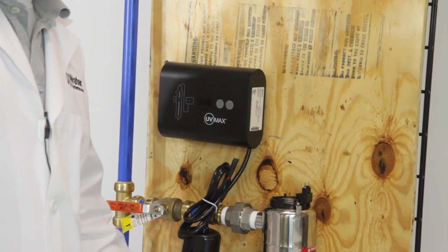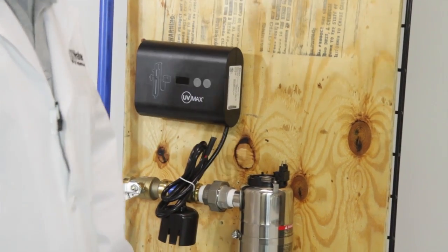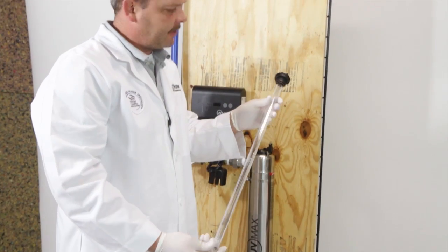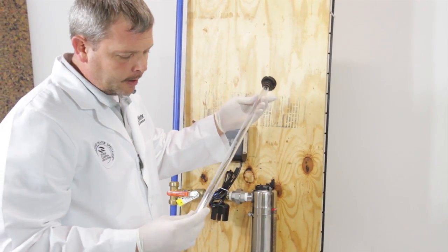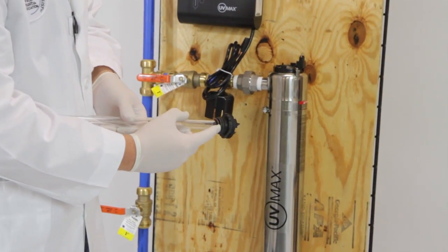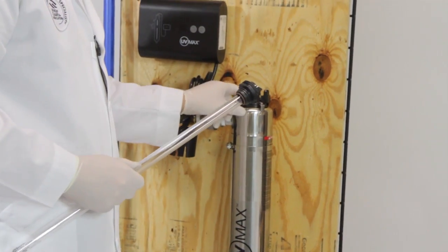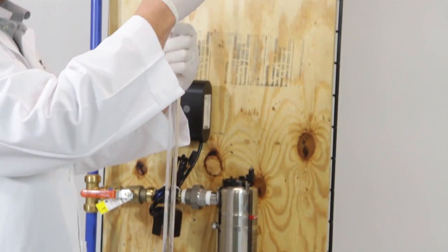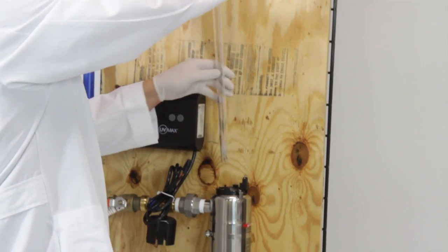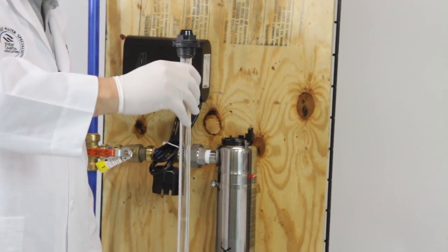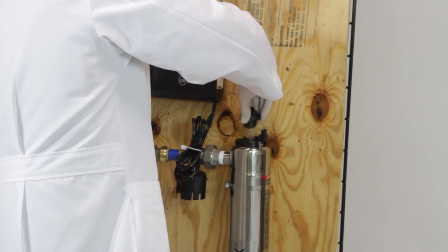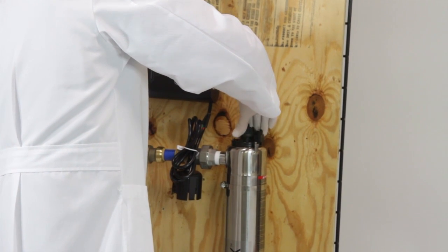Now we're going to install the bulb in the chamber. Again, you want to put your rubber gloves on. We don't want to touch anything here. This is called a bulb-sleeve combo. It's all together in one part. You have an O-ring at the top. This O-ring is what seals this in the chamber. We're going to put it in here and it'll actually thread into place and the O-ring will seal it inside the chamber. Keep in mind, you have this spring in here, so you'll feel this kind of touch the spring when you go down there and that's normal. We want that spring on there for tension because without that spring, water can make this flip back and forth and break. That spring holds it true within the chamber.